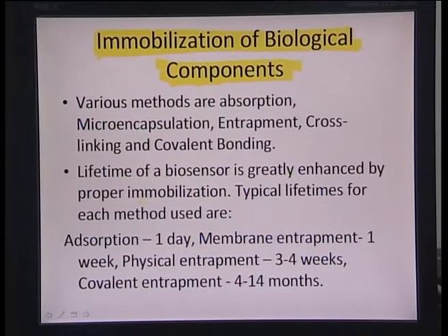So there are various methods for immobilizing. It can be adsorption, it can be microencapsulation, it can be entrapment on a particular electrode or a substrate. You can cross-link or covalently bond a certain biological moiety or entity. Really, the lifetime of a biosensor is greatly enhanced by a proper immobilization technique. If you can choose the right immobilization technique, you can use the biosensors many times reusably without very many changes on the sensor surface.